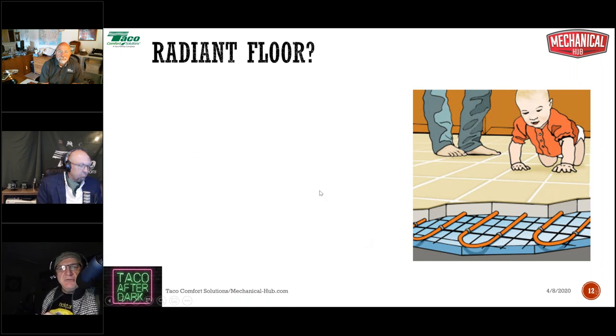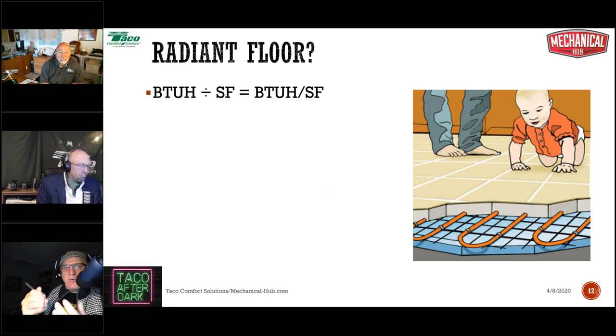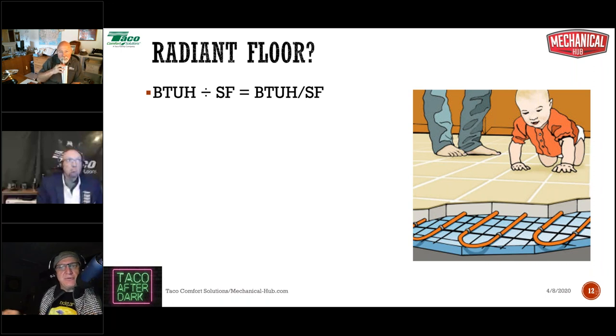No matter which one you choose, you do need to start here. You've got to find out the BTU per square foot requirement. How many BTUs per square foot do I need to get out of this radiator? Okay, the floor is your radiator. We're going back to that cast iron radiator thing. If we took a cast iron radiator and just bulldozed it and made it flat and spread it out over the entire floor, that's what we're talking about.